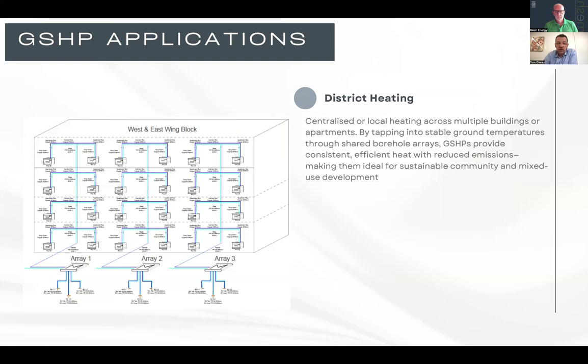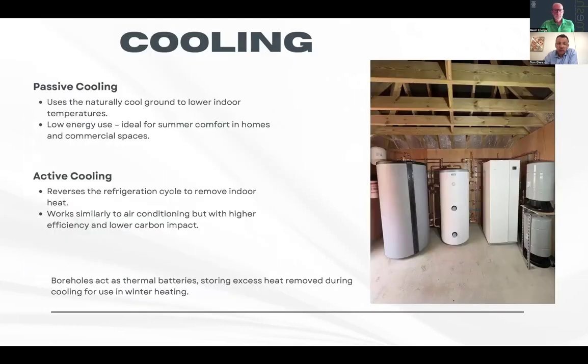The other option is district heating, and there are two versions. You can have a system with a shared borehole array, and then you install flow and return with the glycol to each individual apartment, flat or commercial unit. In a commercial unit, you have an actual heat pump generating heat and hot water. Or instead of array 1 here on this drawing, you might have an energy center, where you generate heating and hot water and then provide this to different houses. We've done a few systems like that where we are heating a few houses from one energy center. Of course, you need to provide suitable pipes to distribute the high temperature hot water, but that's part of the design. More common now, cooling.